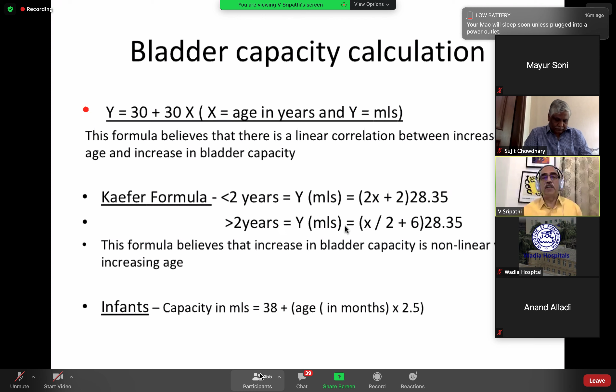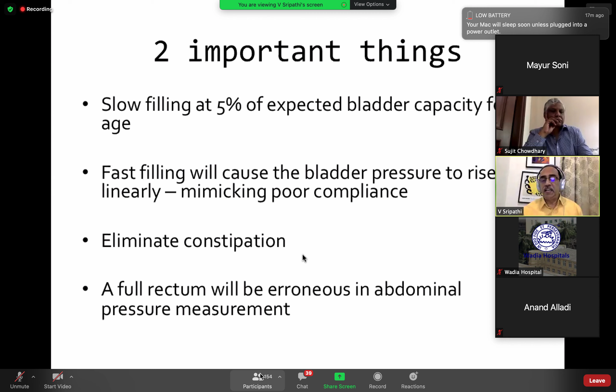So how do you do a bladder capacity calculation? It's very important to know the standard formula, 30 into age plus 30. But if the child is less than 1 year of age, a good formula to follow is 38 plus age in months into 2.5. For those between 1 and 2 years, the Kaefer formula is quite good. Why is this important? Because you have to do slow filling at 5% of the expected bladder capacity for age. A lot of times people fill fast because they want to finish the study quickly and do something else. You will get a linear pressure rise which will mimic poor compliance. You have to eliminate constipation, and a full rectum will not enable you to get a good rectal pressure measurement. This is one of the major problems with putting in rectal catheters.